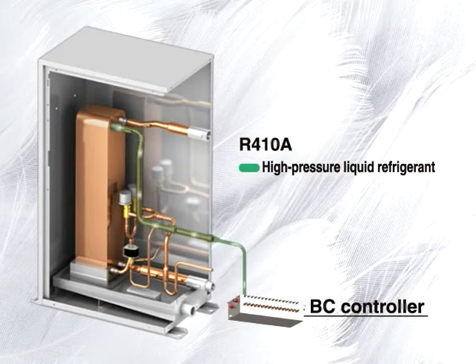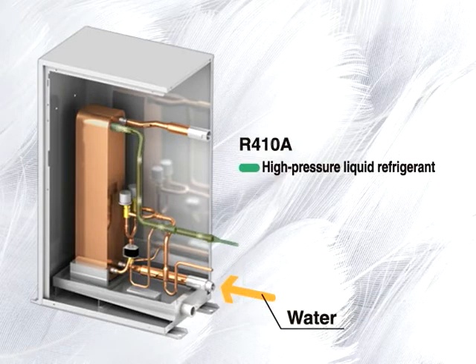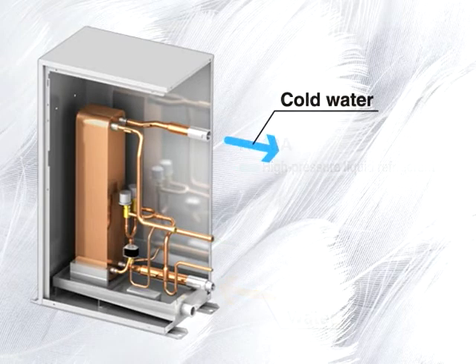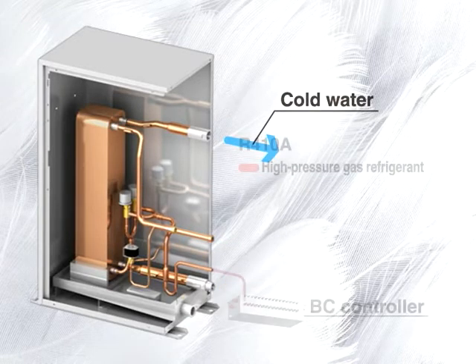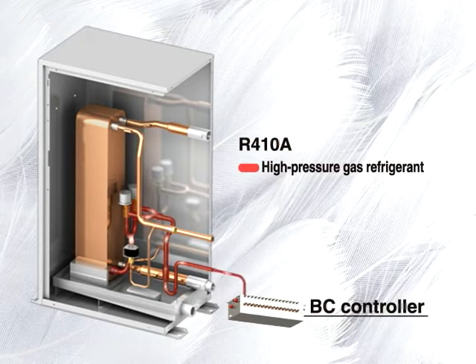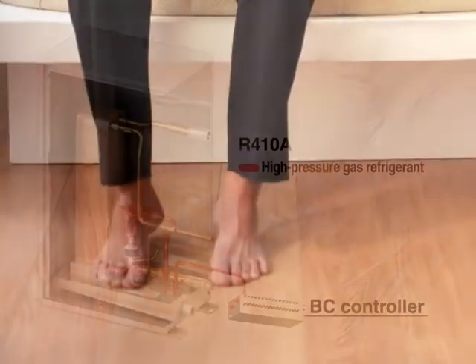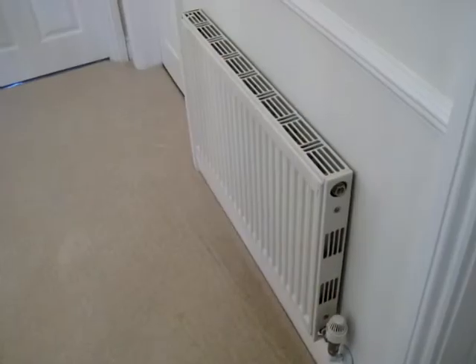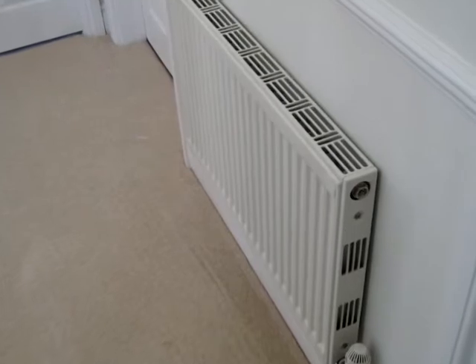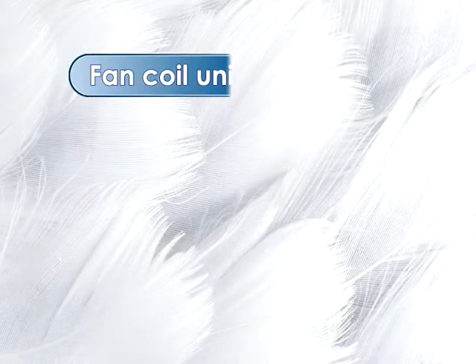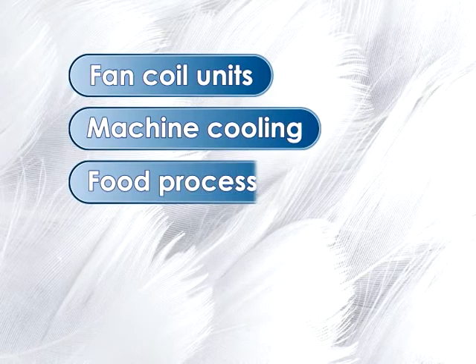Cold water utilizes the cooling operation cycle. It delivers high-pressure liquid refrigerant through a BC controller. The refrigerant heat is exchanged, cooling the water entering the unit. Then, the refrigerant returns to the BC controller as high-pressure gas refrigerant. Hot water can be used for floor heating and panel heaters. And cold water can be used for cooling operations and fan coil units, machine cooling, food processing, flower shops, and for pet and plant preservation.